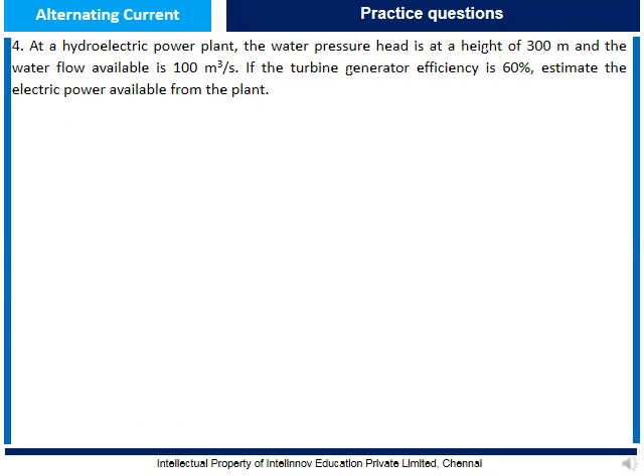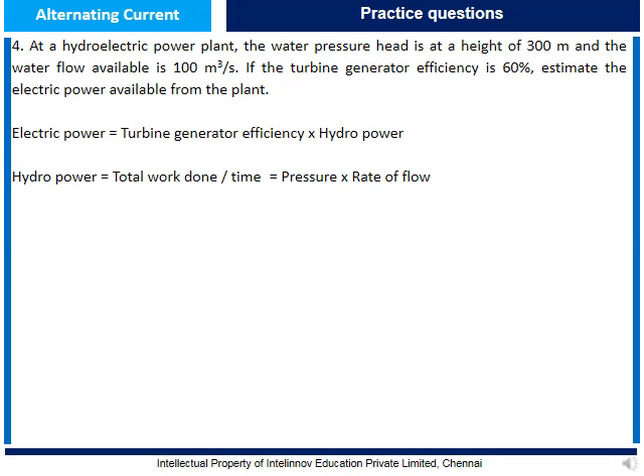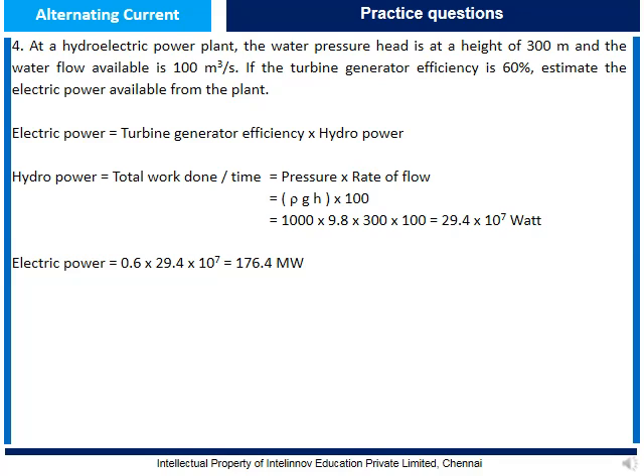Question 4: At a hydroelectric power plant, water pressure head is at 300 m height with flow of 100 m³/s. Turbine-generator efficiency is 60%. Estimate the electric power available. Hydro power equals pressure × flow rate, where pressure equals ρgh. Substituting values gives hydro power equals 29.4 × 10⁷ W. Electric power equals 60% × hydro power equals 176.4 MW.